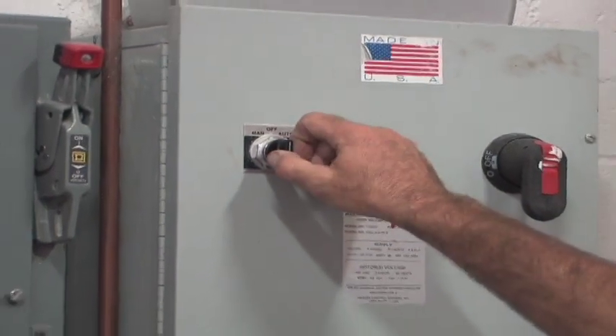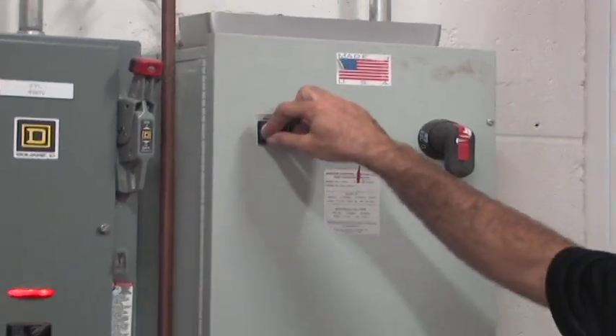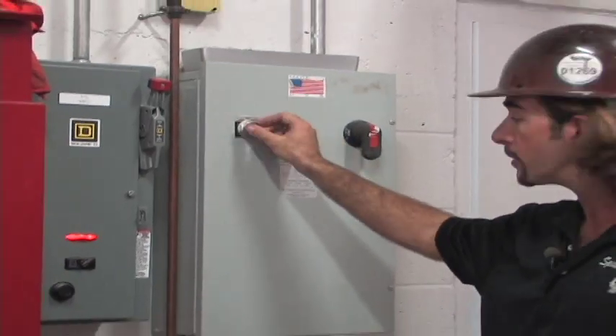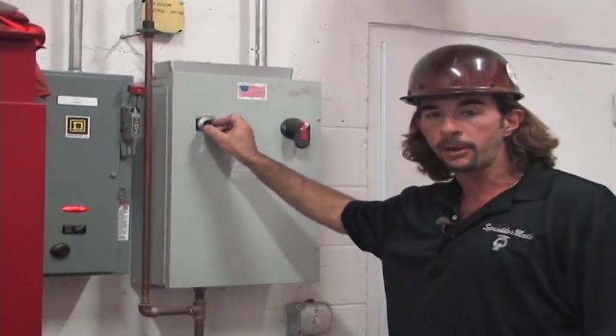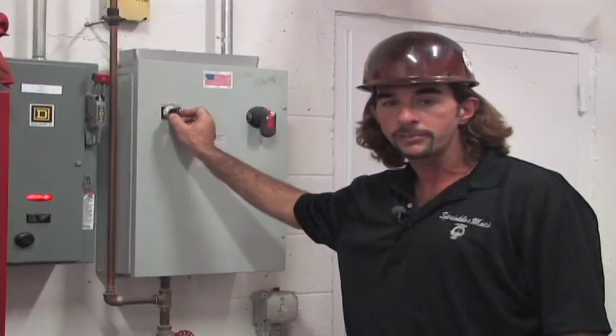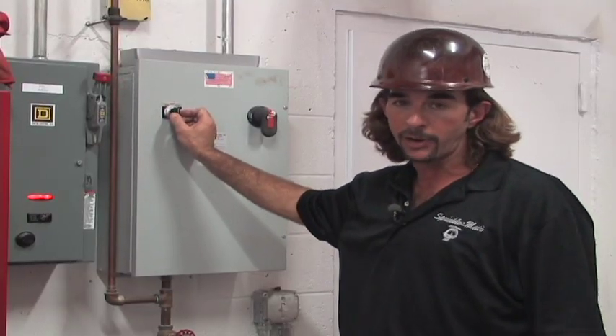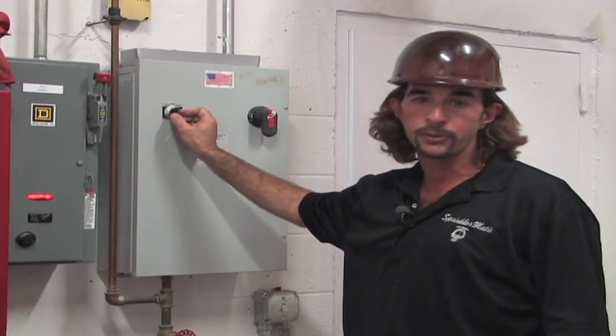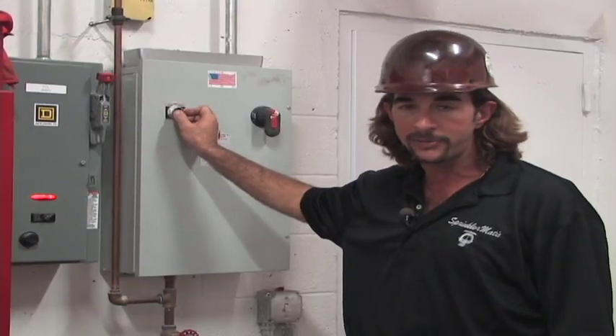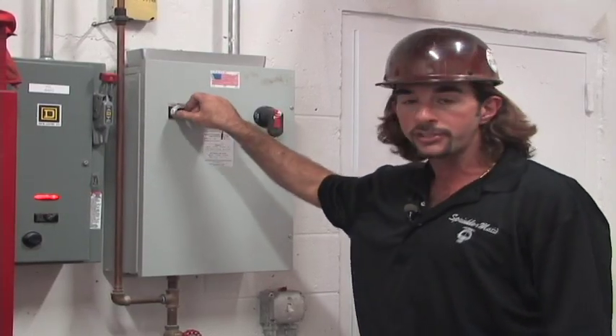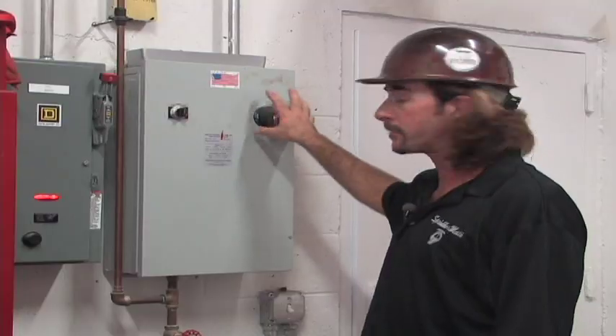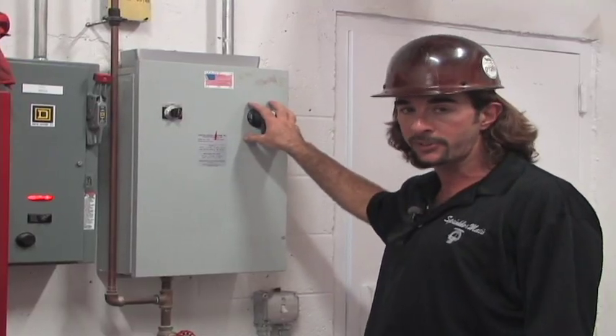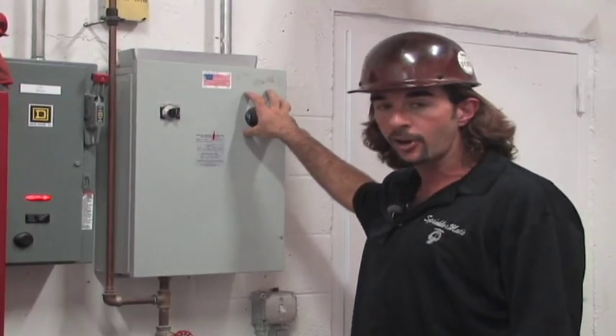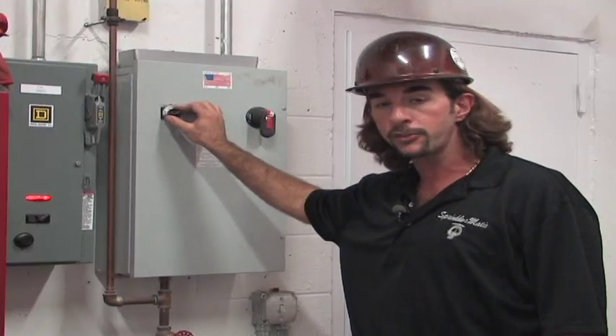We have the off position, and then we have the hand or the manual position, which as soon as you turn that over, the pump is going to run non-stop. It's only going to build up to a certain amount of pressure. It's not going to continue to pump up over 180, 185, 190 psi, but it will stay on the whole time. So we need to make sure that our full-time 24/7, 365, main switch is in the on position and the selector switch is in auto.